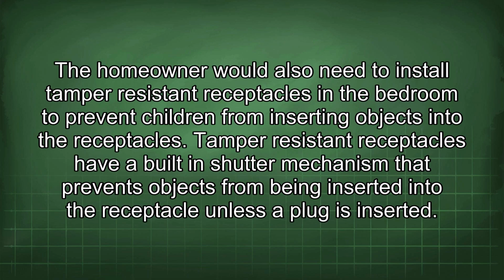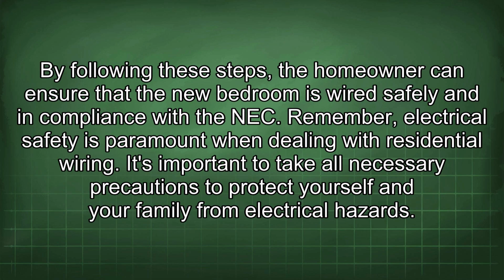The homeowner would also need to install tamper-resistant receptacles in the bedroom to prevent children from inserting objects into the receptacles. Tamper-resistant receptacles have a built-in shutter mechanism that prevents objects from being inserted into the receptacle unless a plug is inserted. By following these steps, the homeowner can ensure that the new bedroom is wired safely and in compliance with the NEC. Remember, electrical safety is paramount when dealing with residential wiring.